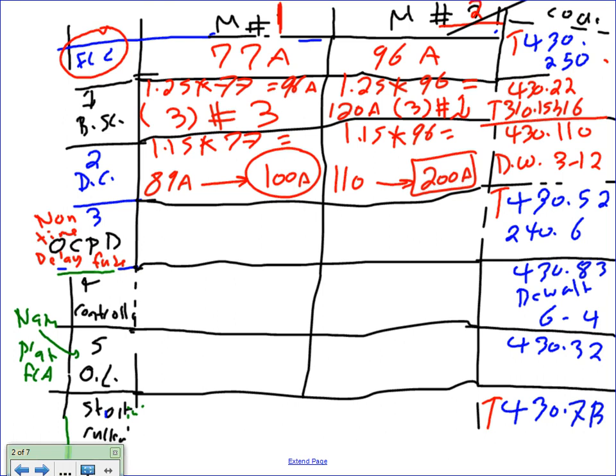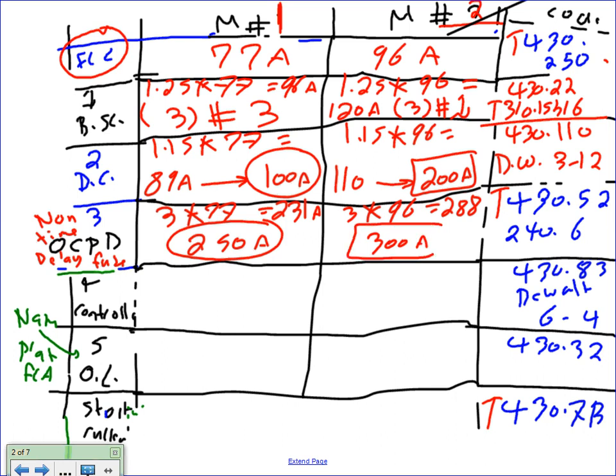I'm glad one of us is awake. 3 times 77, and if you multiply 3 by 77, you're going to end up with 231 amp. And if you go to the next standard, the next standard will be 250 amp. Same thing, 3 multiplied by 96. If you guys go there, 288. The next standard will be 300 amp. Both of them, guys, if it's not a standard, you have to go up.